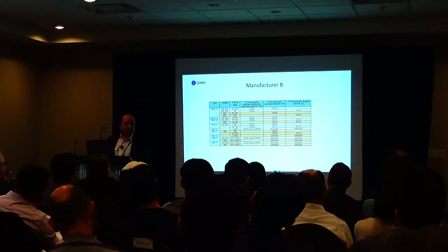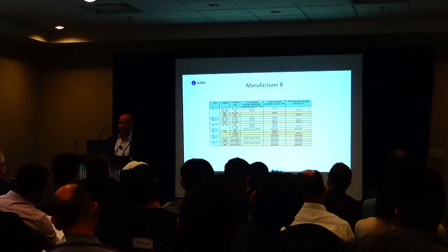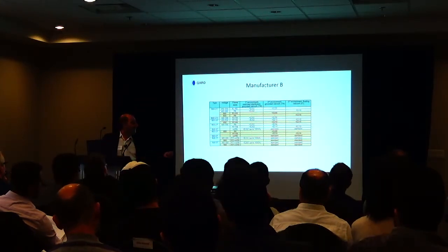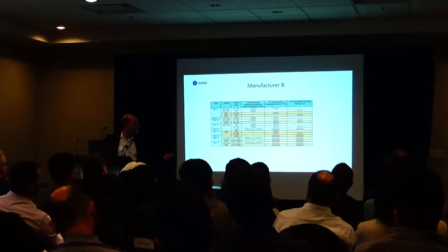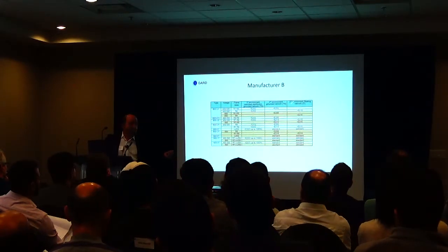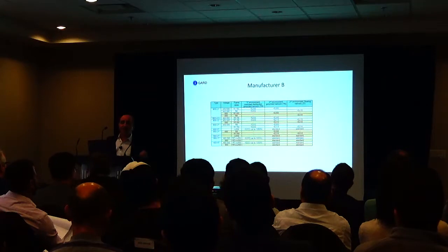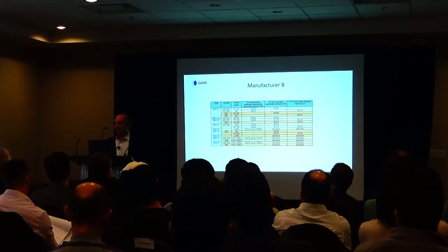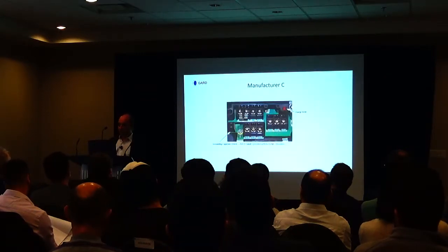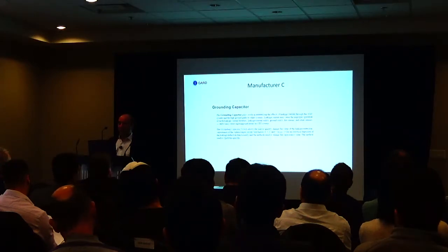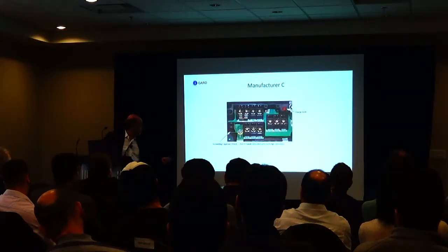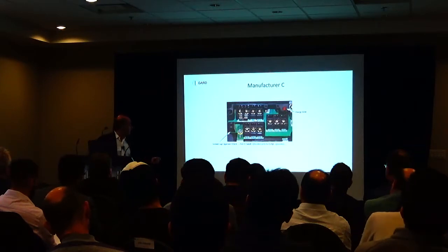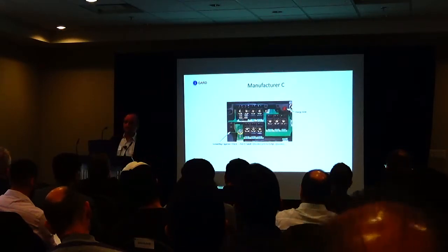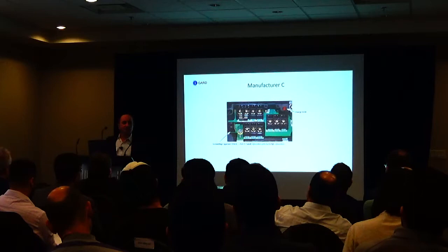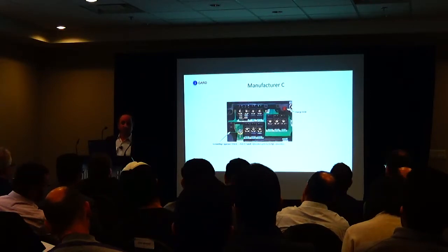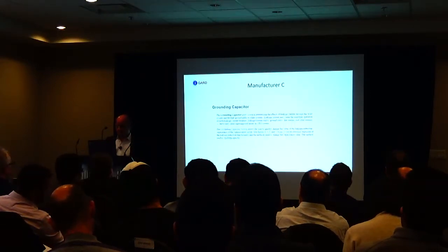Another manufacturer. Anybody do work in Europe? They have a system over there called an IT system, which is different from a TN system. A TN system is a solidly grounded system. IT system is an ungrounded system, because you're looking at potential. Different manufacturer. What they have here is, I love this one, okay? A ground capacitor switch. What does that mean? It means you have to do more reading, that's what it means. Right? So we did more reading.